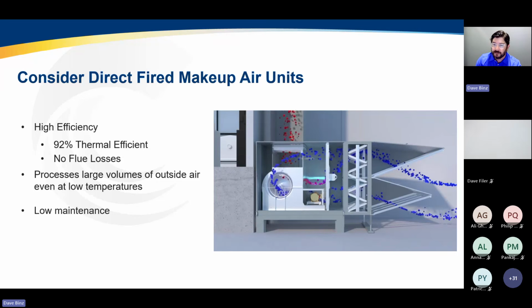It's a 100% combustion efficient process where 92% is sensible heat, 8% essentially is latent heat or humidification, with no flue losses and a fully variable combustion cycle. I can really make sure I'm matching my ventilation needs and my heating needs with no flue losses. So it's highly energy efficient, and we can process large amounts of air in a very simple solution set. So that's why many industrial manufacturers prefer direct-fired makeup air in these applications, because it's a simple system with a reasonable first cost, operating cost and maintenance cost, with minimal moving parts, no large heat exchangers to deal with, no flues, just a simple stainless steel direct-fired burner.